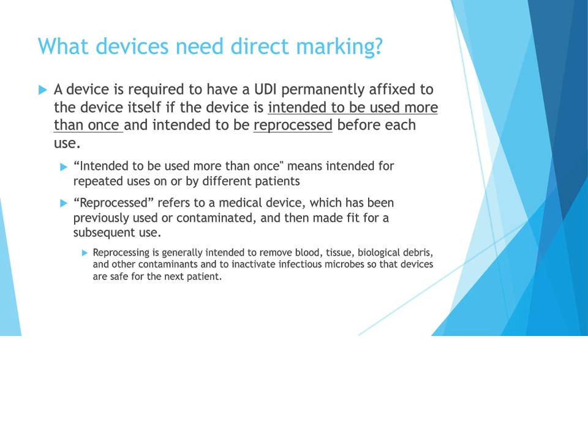In addition to explaining what devices will need direct marking, the guidance does a good job, I think, outlining exceptions to the rule. For example, if any type of direct marking would interfere with the safety or effectiveness of your 510K cleared device, FDA states you would qualify for an exception and would not need to comply. And I apologize, number 2 here is a typo. It should read that guidance clarifies what FDA will expect with regard to submission. For example, if the direct marking will require a new 510K or supplemental PMA. I'll add here that this document is still in draft format, so you can expect to see this guidance finalized as we approach the FDA compliance date.